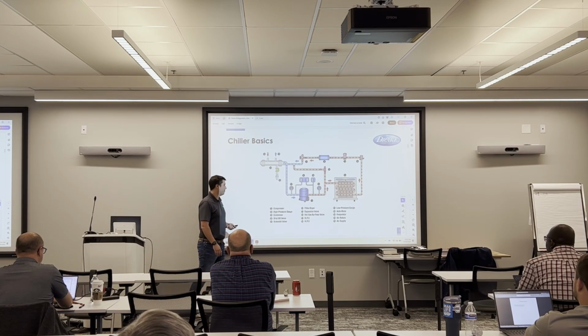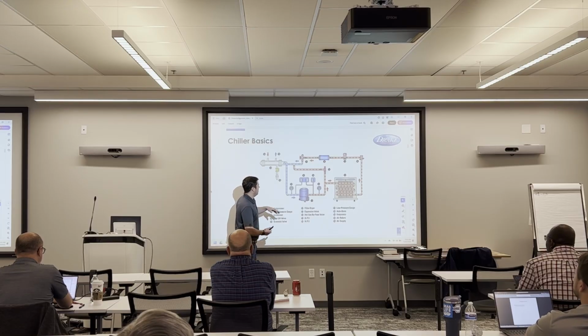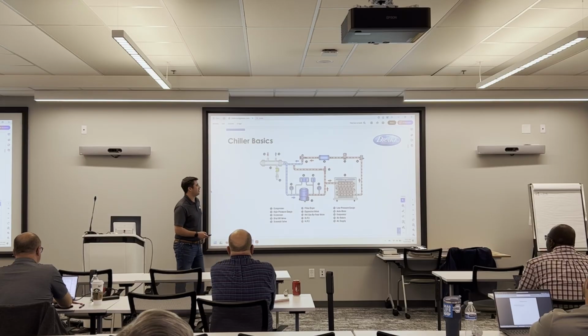As the refrigerant gets compressed, the compressor's adding additional heat to the refrigerant, as well as all the heat that we absorb from the water circuit, and it's going to travel into our condenser coil. There are different types of condensers that you can use. In this example, we just have an air-cooled condenser, a fin-and-tube coil with a fan.